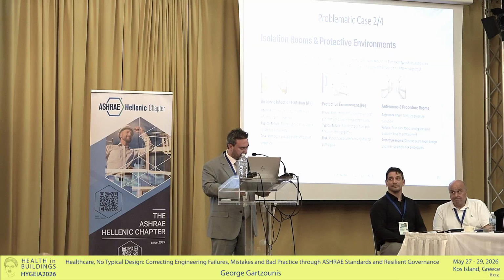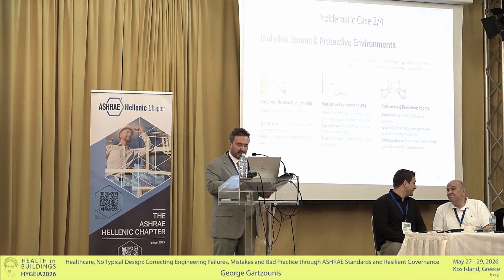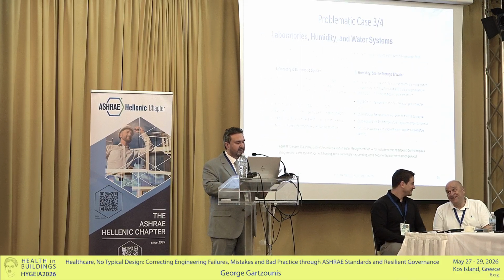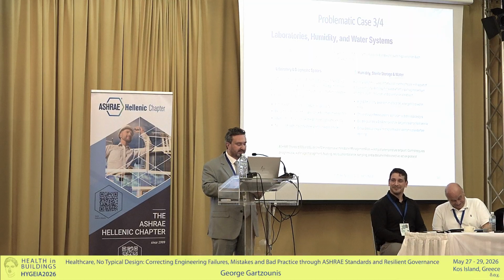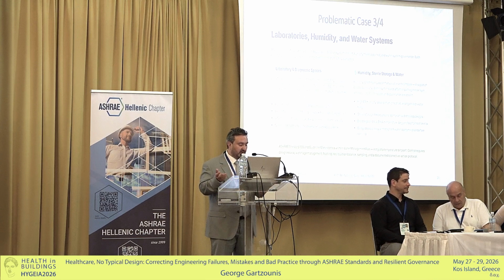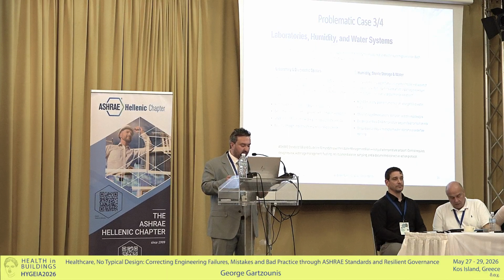I'll leave some stuff out because the panel here is going to keep me alive. Then we have laboratories, humidity and water systems, most of what we examined the last three days. Laboratories are no simple support spaces - they may include chemical exposure, biological risk, odor, pressure balance, fume exhaust, high loads, and staff safety requirements. Same with humidity and temperature failures.